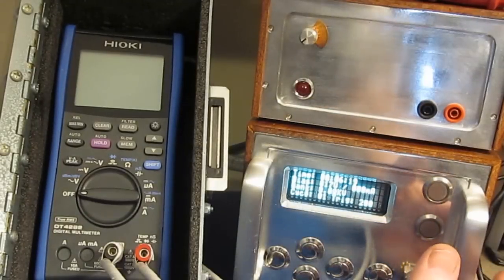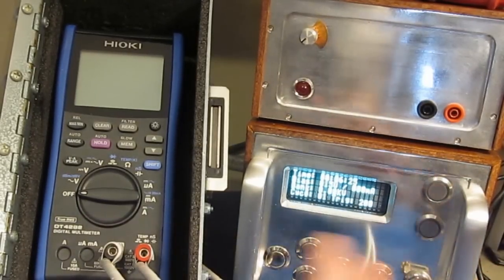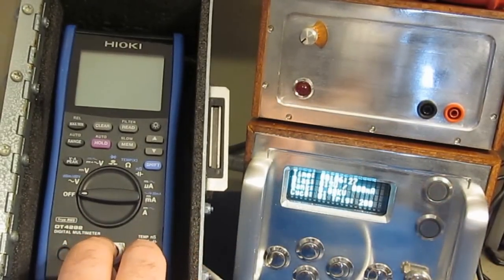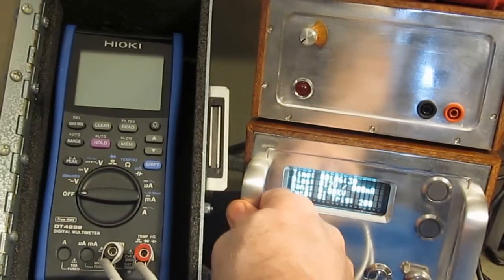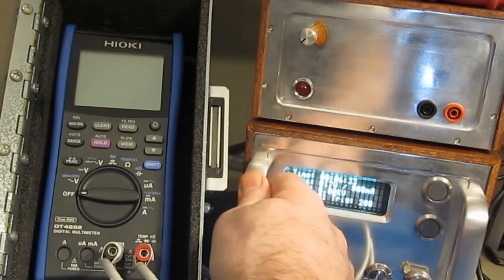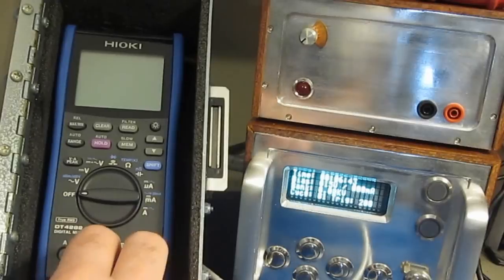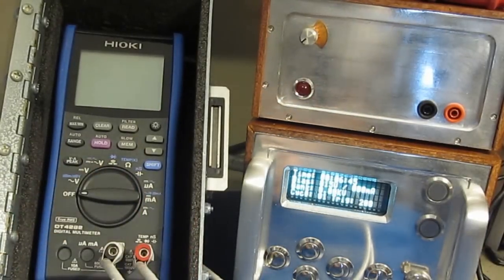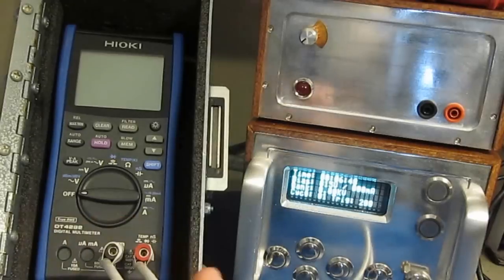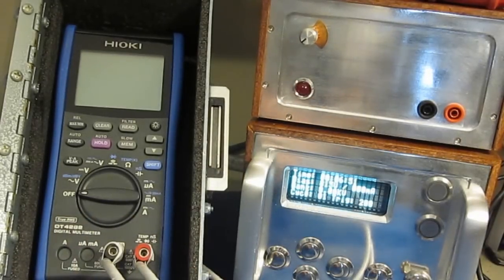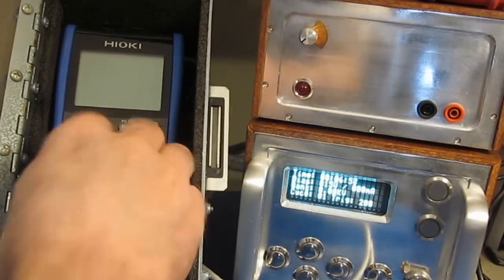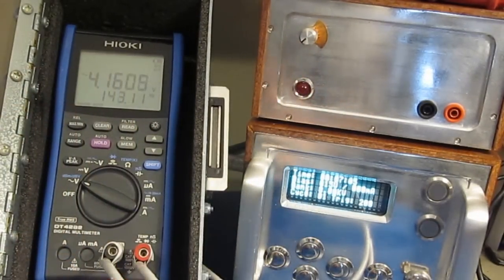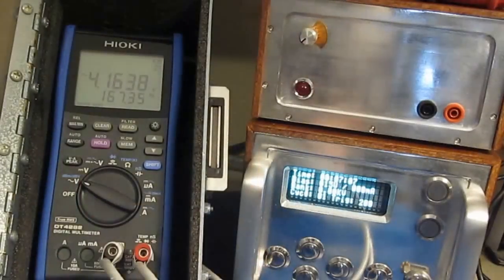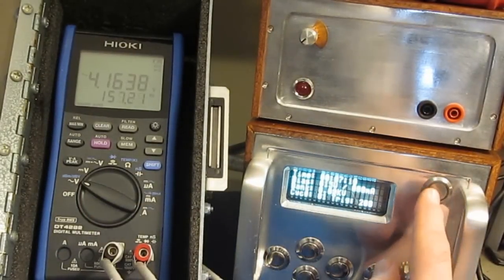So this transient generator is limited to about 20 joules. But again, if the meter does not break down, all that energy is dissipated inside of the transient generator in the output network. So typically that energy is not being dissipated by the meter itself, only if something goes wrong. Now, I'm not going to be using the oscilloscope today to monitor these waveforms. We're still in the summer months, so the room up here is a little hot, so I don't want the added heat. But if it does fail, we'll probably hear it. Typically the meters will click, you can hear them break down, or you'll see the display start to flake out a little bit.